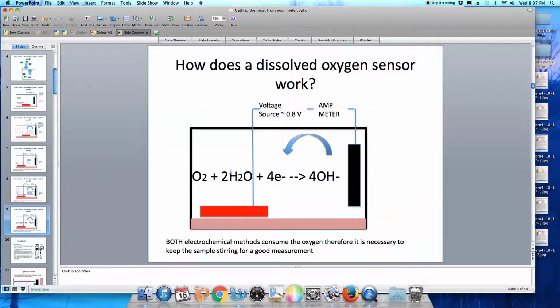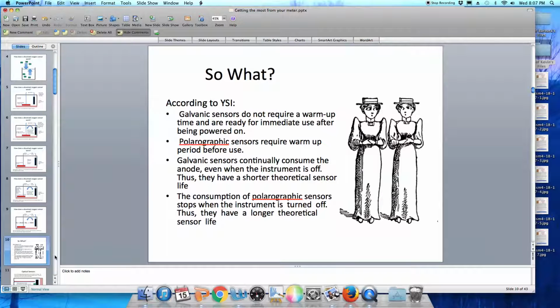So eventually there'll be no more dissolved oxygen in the electrolyte solution, there'll be no more dissolved oxygen just outside of the membrane. So it's necessary to keep the sample stirring or to keep the probe gently swirling or gently moving in the water so that fresh dissolved oxygen is always available to migrate up through the membranes. Okay, so what?